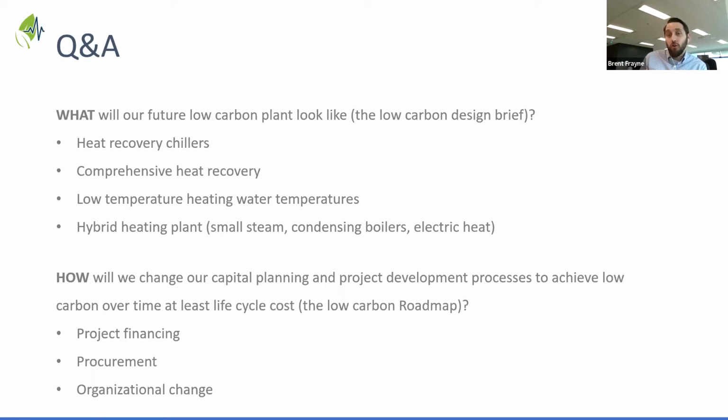Electrify completely. You could, but could you accommodate that with the electrical infrastructure? Probably not. On Corner Brook, we did end up going electric on the steam production side for both humidification and sterilization. And when our electrical engineers did their calculations to figure out how big the electrical service should be to get into the building, they essentially fell off their chairs, right? It was the largest electrical service they had ever seen, larger than what we brought into, say, Humber River. And this is a facility that was probably about a third the size of Humber. So it's probably difficult to meet heating and cooling needs of most facilities in a net zero way without somehow potentially incorporating geothermal in the future.